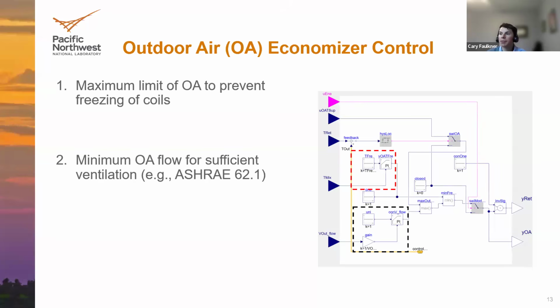So then the second priority is to provide the minimum outdoor airflow for sufficient ventilation, for example, defined by standard 62.1 for commercial buildings. You need to be able to provide sufficient ventilation to make sure people aren't having discomfort and are able to breathe fresh air. So that's the second priority, just ensuring that you're bringing enough outdoor airflow to meet that set point. And so similarly, there's going to be a PI block associated with that.